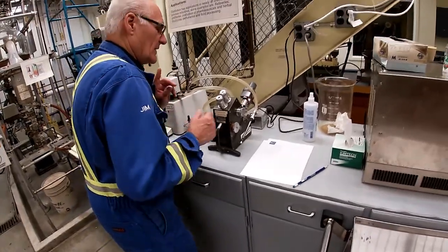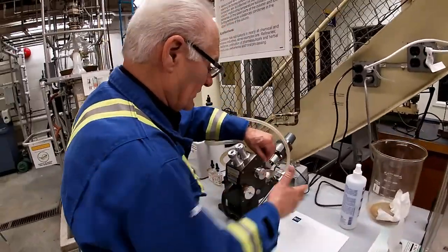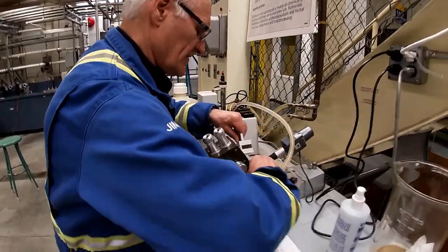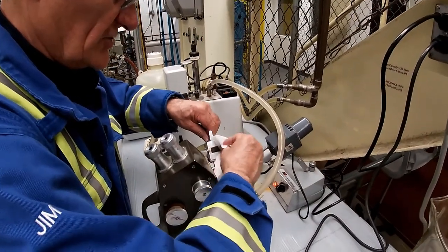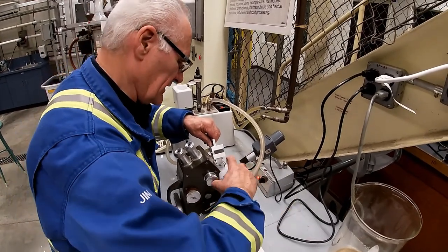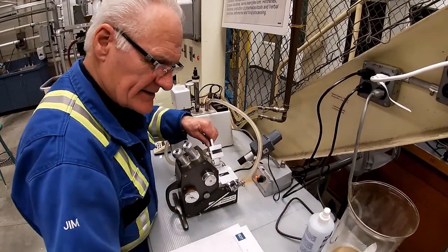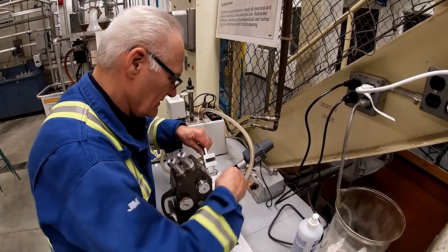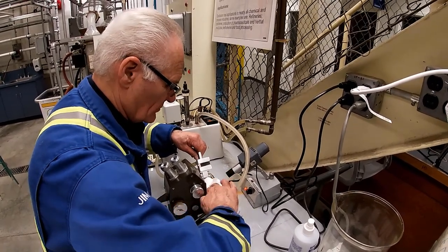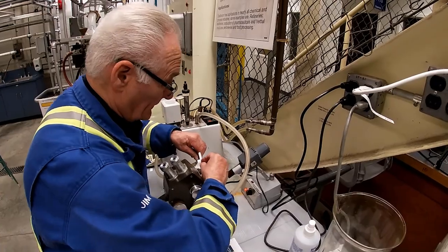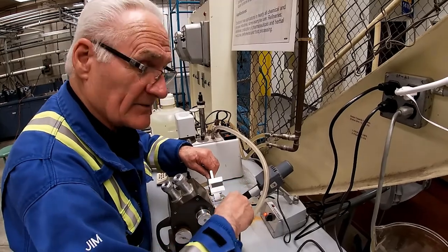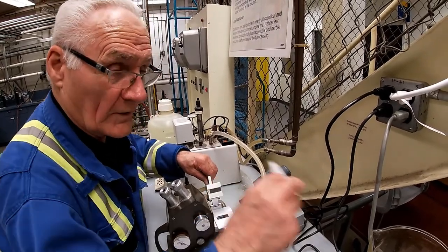Okay, so then I'm going to pull this guy out of here, and grab one of the samples I had from my previous test, just so that you can see how they actually shift. Again, clean. Cleanliness is next to godliness. I really got messed up with this thing when I was first trying to get it running, because it had been sitting here for years and nobody looked at it. For love nor money, I could not get this thing to work. Then finally I thought, I wonder if that glass is clean or not. So I got some glass cleaner, I cleaned it, bang, just like magic, it all worked.